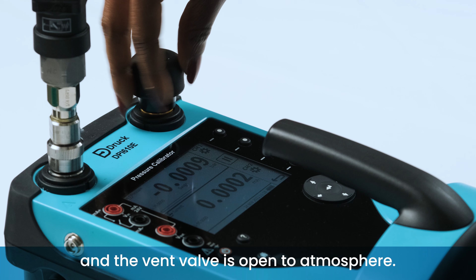The DPI610E provides switch test functionality to enable pressure switches to be tested and adjusted to ensure correct and reliable operation. Ensure the pressure connections between the DPI610E and the pressure switch are secure and the vent valve is open to atmosphere. Check that you have the correct pressure function selected on channel 1.